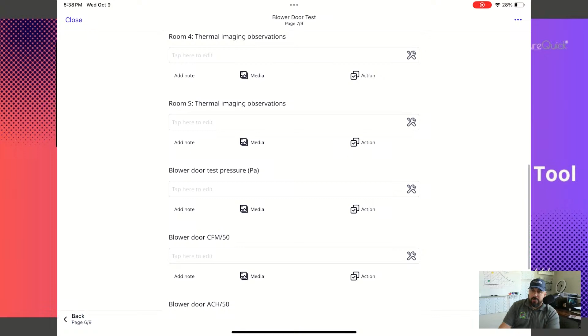What I'm going to do is turn on that blower door - I have a Retrotec blower door - and just barely depressurize the house to around 20 to 25 pascals. That starts bringing in some of the heat and moisture if I'm doing it on a hot day. But if I do the full blower door test first, I'll pull all that stuff in and then it'll be harder to see on the thermal imaging. So I start with just barely depressurizing the house.